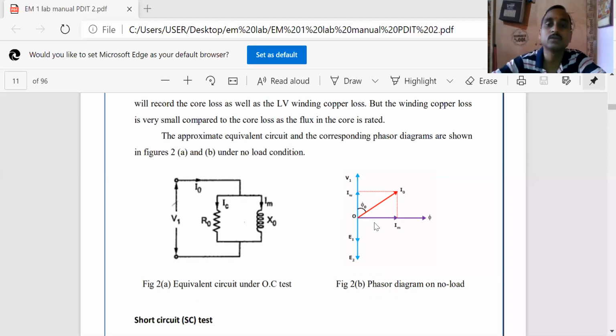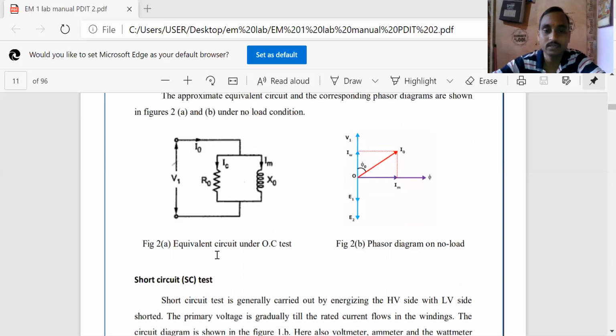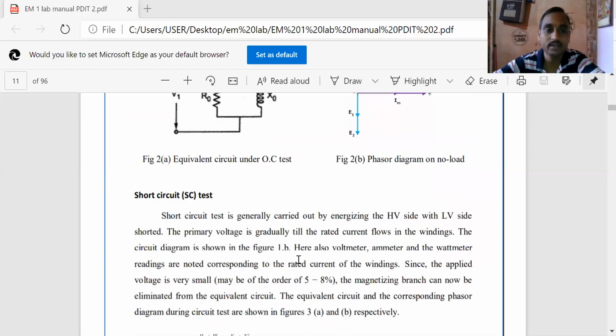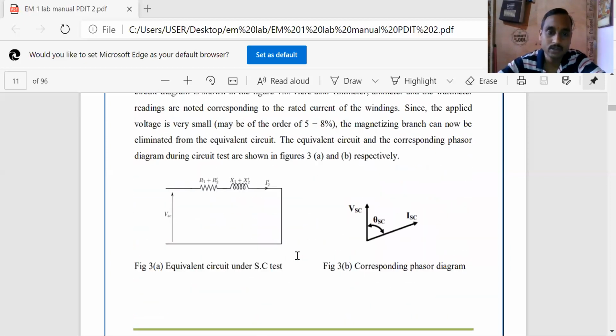So the angle between IW and I0 is called phi naught, the no load angle. This is the phasor diagram under no load condition and the equivalent circuit under the OC test. And for the short circuit test, we use the resistance of the primary side and the resistance of the secondary side, and the reactance of the primary and the reactance of the secondary side, referred to the primary side.